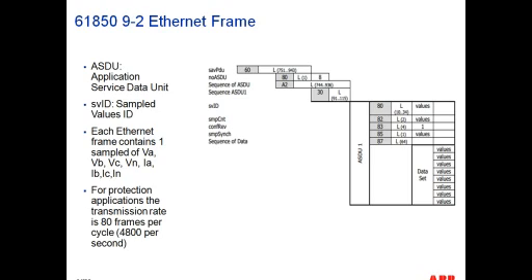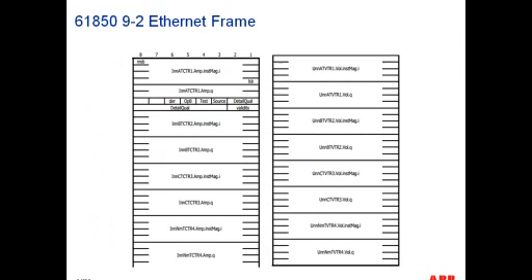One sample for your phase A voltage, one sample for your phase B voltage, one sample for your phase C voltage, one sample for your neutral voltage, one sample for your phase A current, one sample for your phase B current, one sample for your phase C current, and one sample for your neutral current. And for protection applications, we're going to essentially send 80 frames per cycle because we're sampling that cycle 80 times, which results in 4,800 frames per second. So that's just to give you essentially an idea.